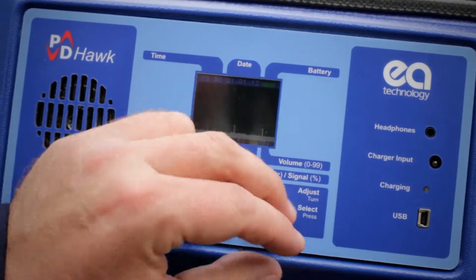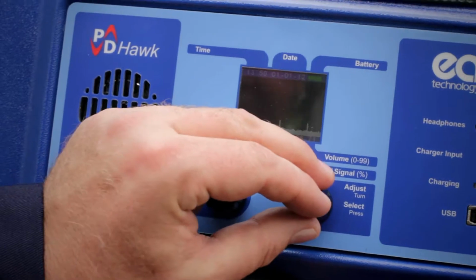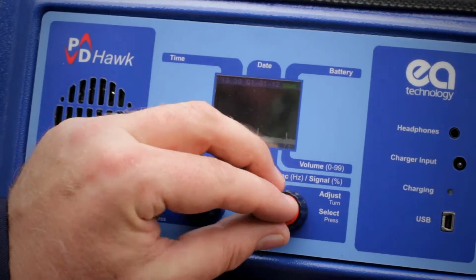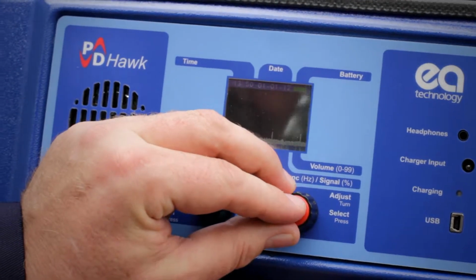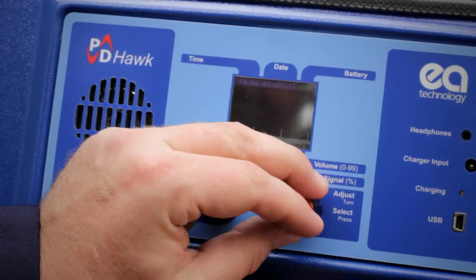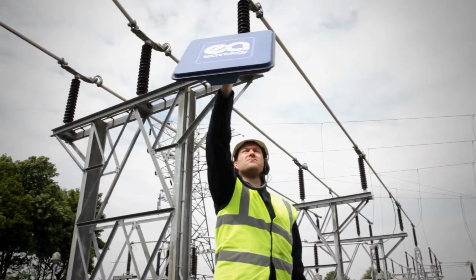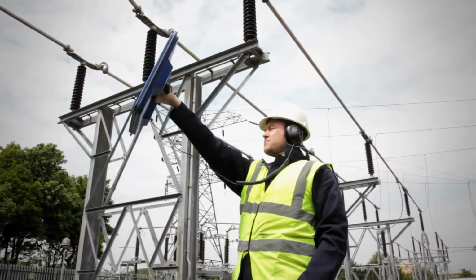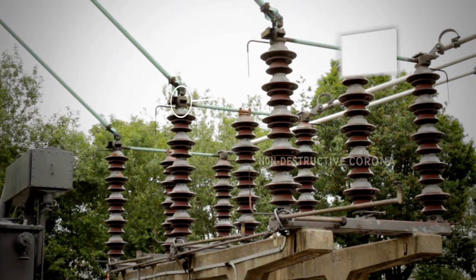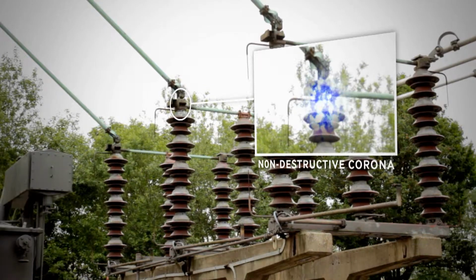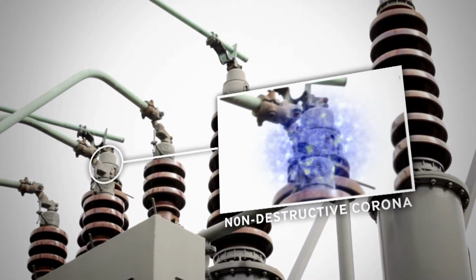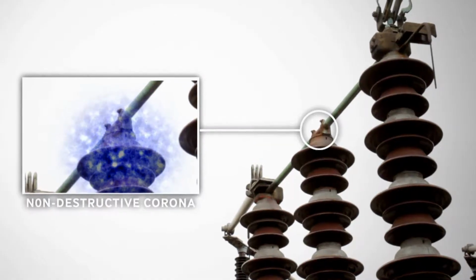Many switchyards are subject to different types of radio noise, including television and mobile phone transmissions. These are normally at fixed frequencies, and with the PD Hawk, they can be tuned out. The instrument is also designed to ignore non-destructive corona activity, because it is at a different frequency from the PD activity we are looking for.